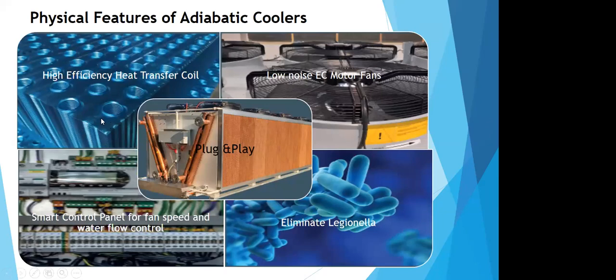Finally, we'll look at some of the features of this adiabatic cooler. As I told you in the beginning, it consists of two coils. These are highly efficient heat transfer coils made of copper tube and aluminium fins, which are arranged in a corrugated fashion, maximizing the heat transfer. And on top of these are the fans. These are compact EC fans with an aerodynamic blade design, which minimizes the noise level by almost 8 to 10 dB as compared to a standard fan.